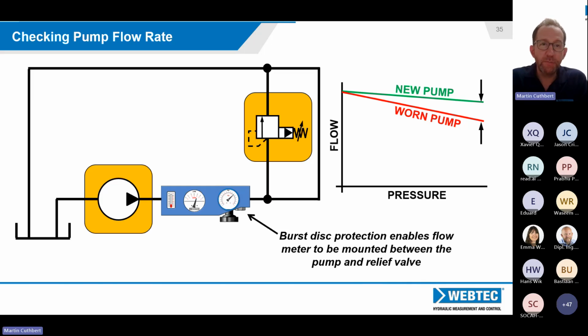The Interpass safety system, if you like, is burst disk protection, enables the flow meter to be mounted between the pump and the relief valve. Why is that? Well, the burst disk protection will prevent you from over pressurizing the tester. So it has standard burst discs that are rated to 6,000 psi, 420 bar, and so you won't be able to exceed that, otherwise the burst discs will rupture. As the service engineer, you'll have to keep an eye on what is the rating of your relief valve and your pump and your hose, because they may be rated only to sort of 250 bar, in which case you've got to be aware of that when you're testing it, or change the burst discs for some lower pressure ones in order to make sure you don't exceed that. But there is a safety system there available, which will give you some protection, despite the fact that you're installed in the circuit before the relief valve.